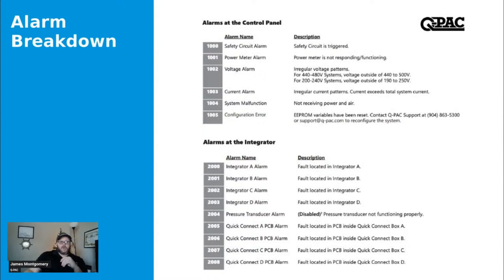Moving on. So these are the more common ones, the integrator alarm. So 2000 through 2008. We talked about the control panel and the quick connect configuration. So quick connect A, or the first quick connect, can hold up to 9 fans in our system. You may not have 9 fans. You may have 5 or 4 or any variation therein. When you start to grow above a 9 fan system, we will typically balance those out. So we'll put maybe 4 fans on the first quick connect and 4 on the next. We can do up to 9 on each of those.